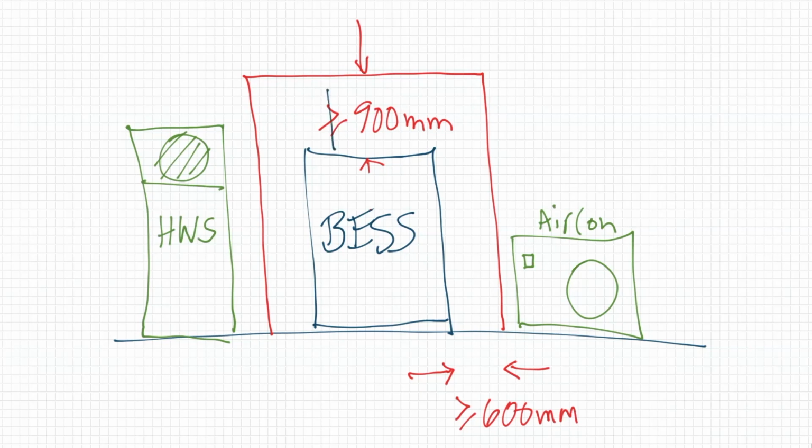So let's say we've got an inverter here. That's okay as long as your clearances are as per the manufacturer's recommendation. You might have an isolating switch, you might have some monitoring equipment as well, etc. That can be within that 900 mil high, 600 mil exclusion zone.